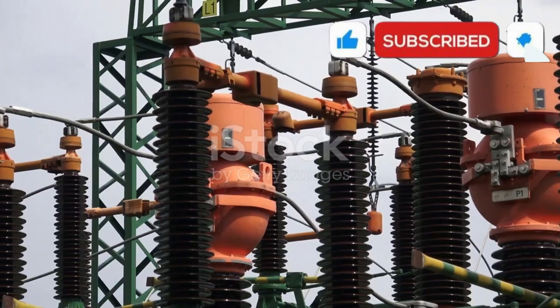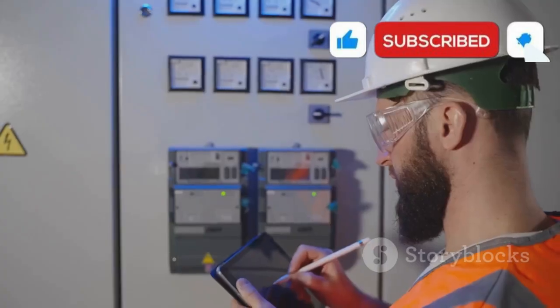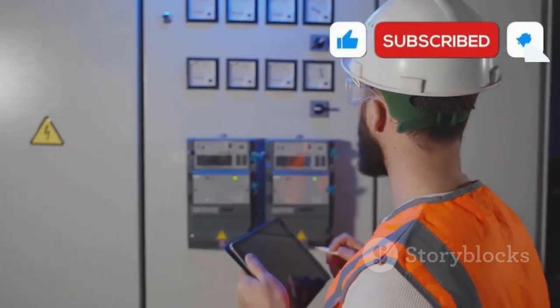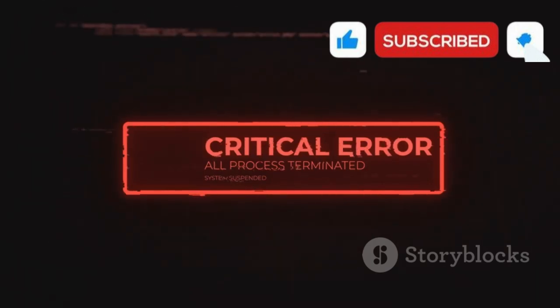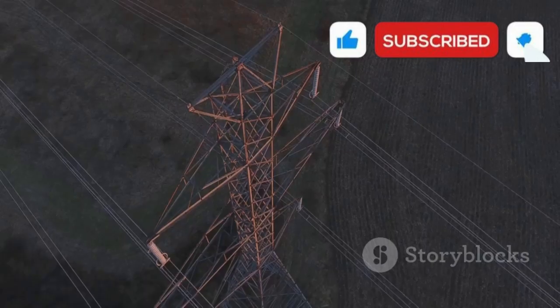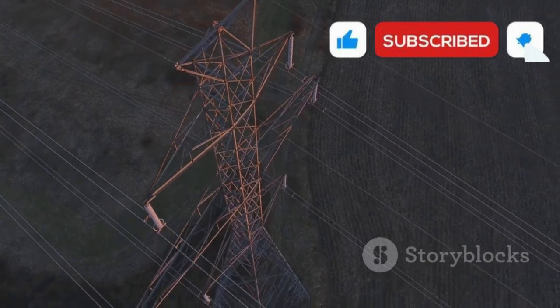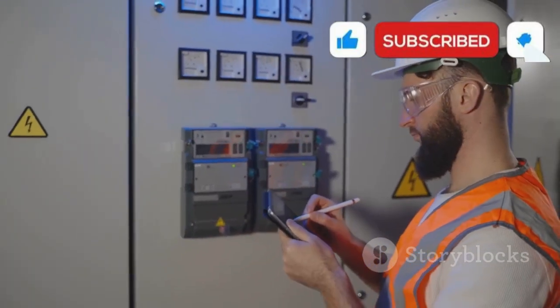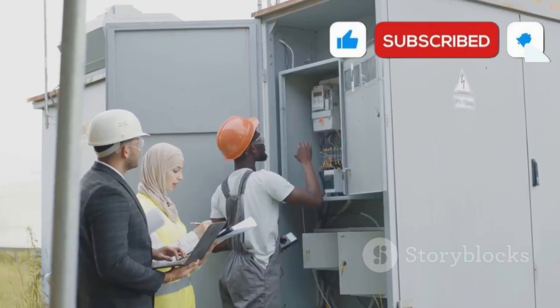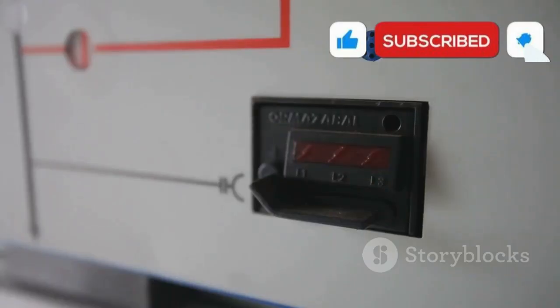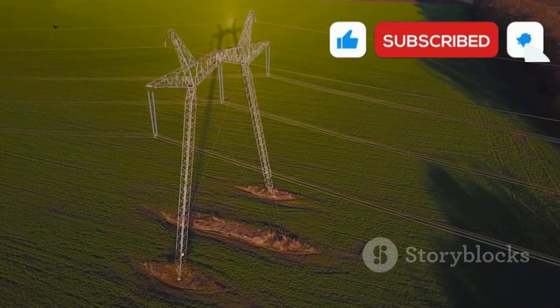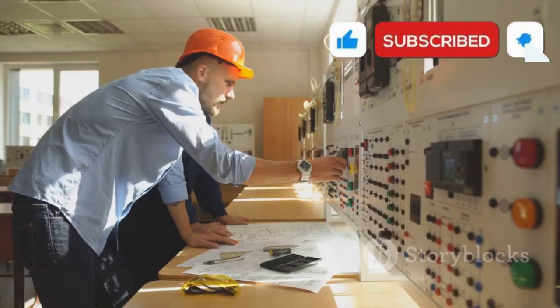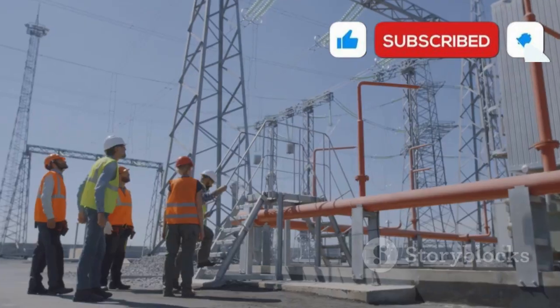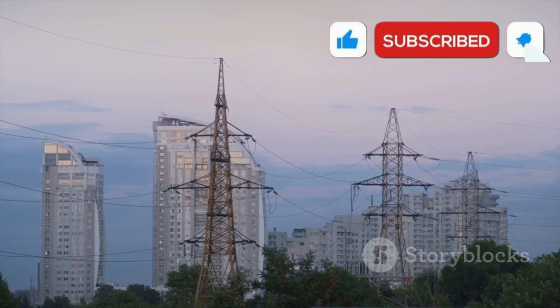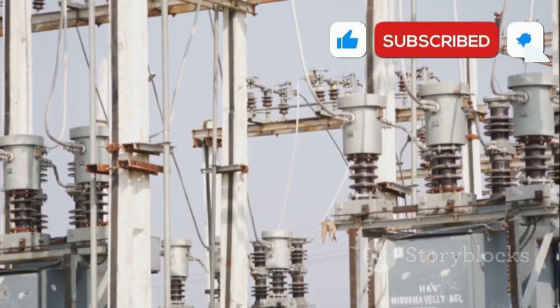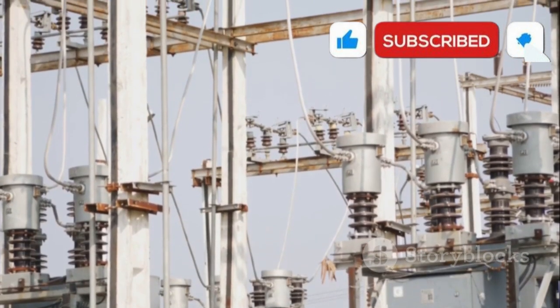Relays and breakers are vital but not perfect. Sometimes they fail, due to miscalibration, software bugs, or mechanical issues. If a breaker doesn't trip, the fault can spread, causing larger outages. Hidden failures can lurk undetected until an emergency. Regular testing helps, but some issues persist. And if a cascading failure is too big or too fast, even perfect protection can be overwhelmed. The grid's bodyguards can win battles, but sometimes lose the war. That's the fragility of even well-protected systems.